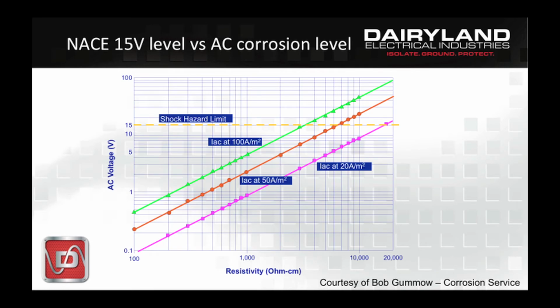Here's a useful graph that can show quite a bit of information. We have AC voltage on the vertical axis graphed against soil resistivity on the horizontal. You'll notice that at 15 volts, you'll see the horizontal line with the yellow dashes representing the NACE 15-volt criteria. You'll also see some brightly colored lines crossing this graph, and that is current density shown in amps per square meter with some typical industry agreed criteria shown on there. The pink line on the bottom represents a current density of 20 amps per square meter up through the green line, which is a higher current density of 100 amps per square meter. And those are generally given as the lower and upper limits to current density awareness or warnings to the industry.